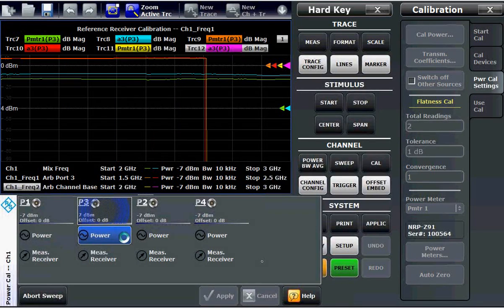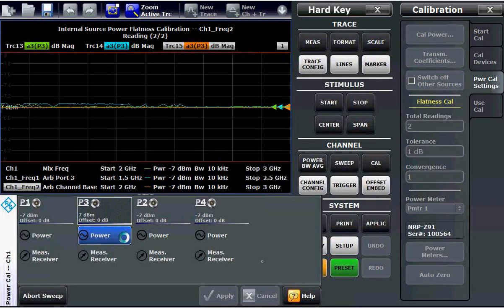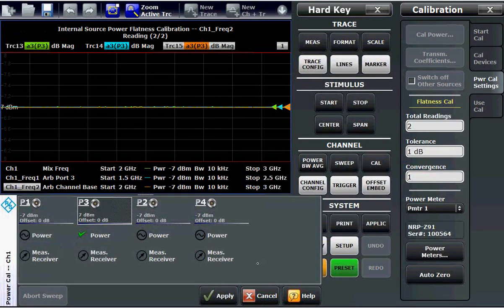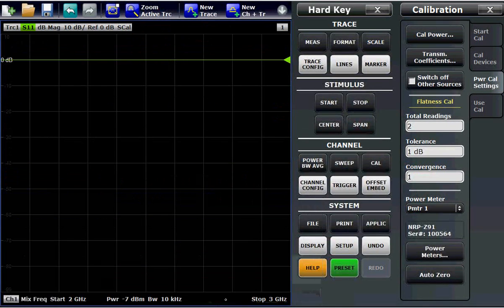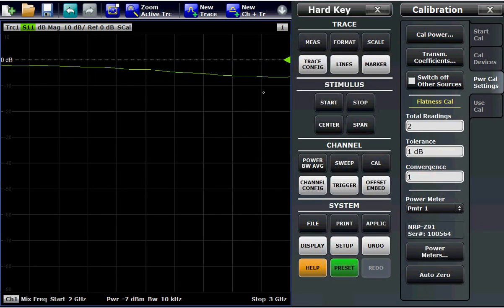The ZNB performs the source power calibration and the flatness calibration. After finishing this calibration, we have to press the Apply button, and now the ZNB is ready to do the mixer measurement. Therefore, we have to connect port number 1 to the RF port of the mixer, port number 2 to the IF port of the mixer, and port number 3 to the LO port of the mixer.